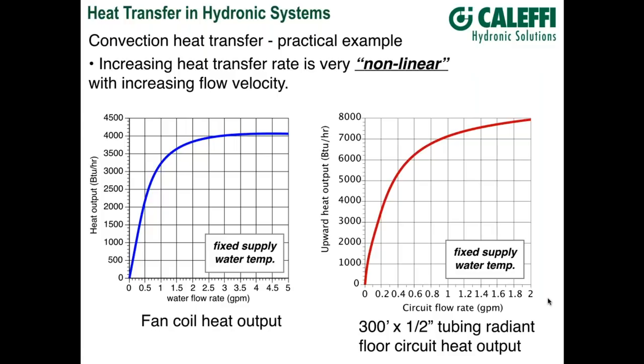A 300-foot circuit of half-inch PEX tubing in a slab — holding the water temperature at a fixed value and varying the flow rate — shows a rapid increase in heat transfer at low flow rates, then diminishing returns at higher flow rates. These are the reasons behind things like equal-percentage balancing valves: the idea of creating a valve so we get an approximately linear relationship between heat output and flow rate. You can't do that with a standard globe or ball valve — you need a characterized valve with an equal-percentage characteristic.